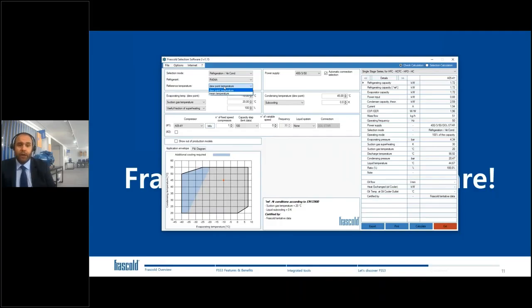Usually the selection is done in dew point temperature, but if you use a refrigerant that has a high glide temperature, it may be more useful to make the selection at mean temperature, depending on your preferences. We also have the possibility to select different power supplies that are all available for the compressor. If you see a power supply in this box, it means that it is available for the compressor selected.